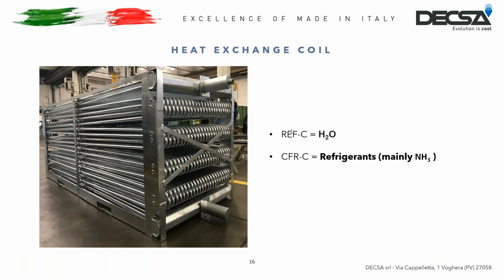So, the exchanger coil. It consists of coils made of hot-dip galvanized carbon steel. In the REF model, the fluid inside is always water. In the CFR model, the fluid inside is a chemical compound, mainly ammonia. This is the only difference between the two models. Obviously, I mean REF and CFR.